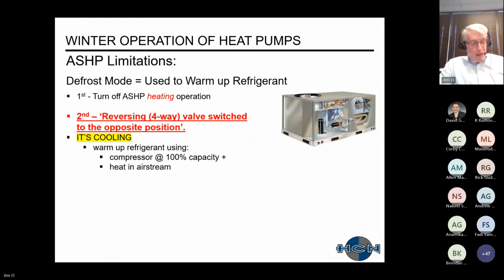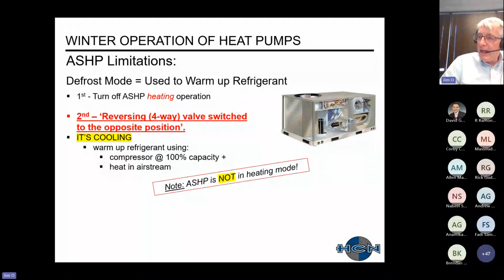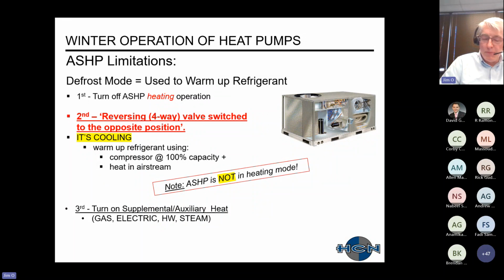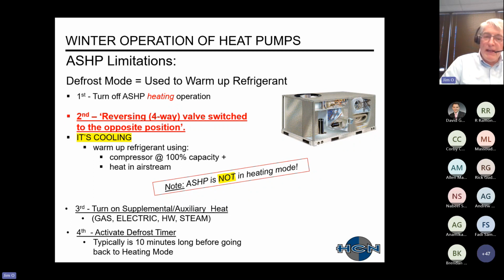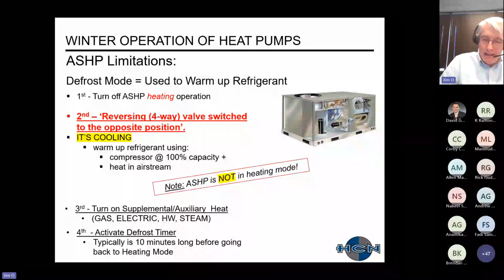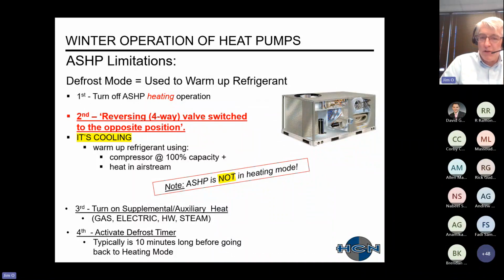And then in addition, we'll heat the refrigerant that's in the airstream with the combination of return air and outside air. Then what will happen next is that the rooftop unit or the split system will turn on its supplemental auxiliary heating. This, as I said, can be gas, steam, electric, et cetera. And then we'll also activate a defrost timer that typically is 10 minutes long before it's allowed to go back into heating mode. Want to just emphasize once again, as that box in the center says, when you're in defrost mode, your air source heat pump is not in heating. All right, you've got to make sure you realize that, and it is going to occur.